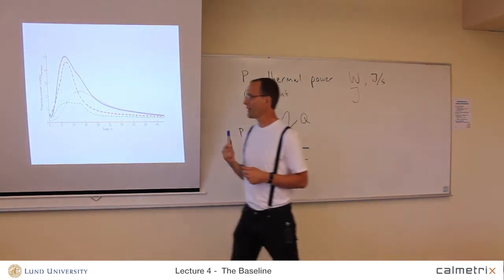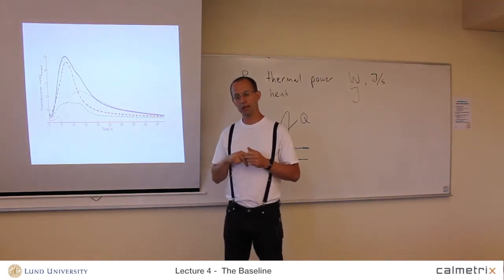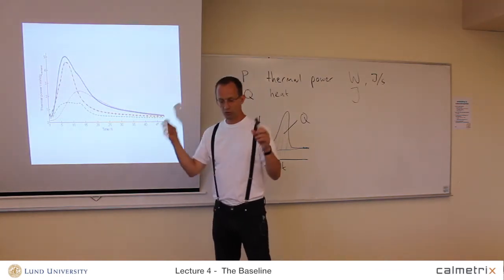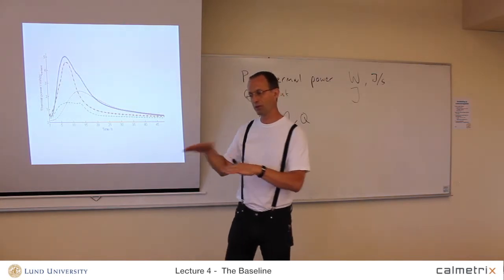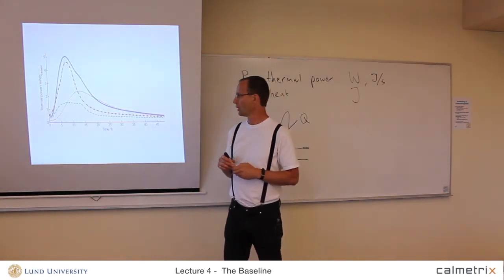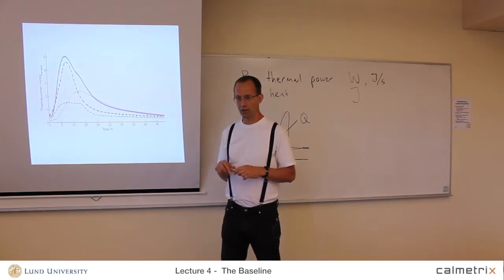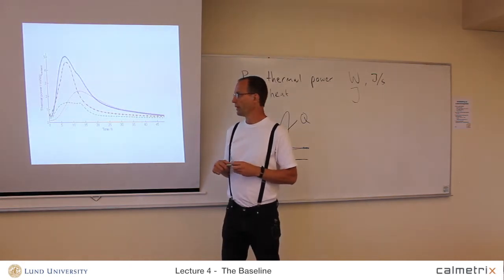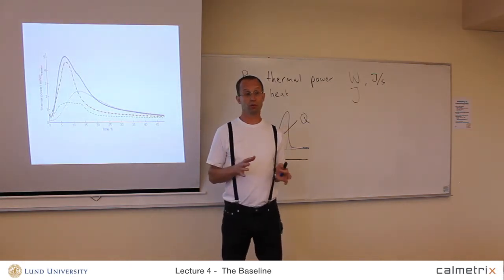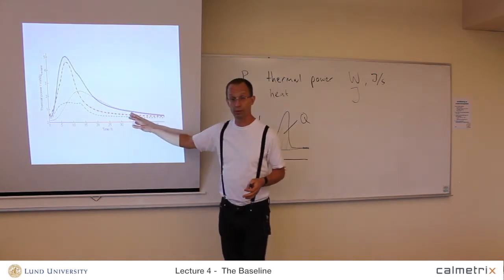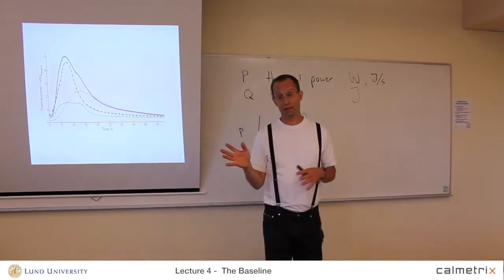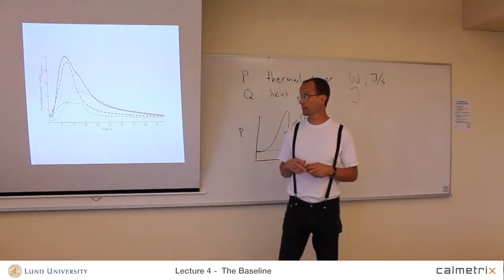To measure good baseline values, one should measure for quite a long time — at least 24 hours — because when you put things into the calorimeter there can be some initial disturbances. So measure for at least one day. On the other hand, baselines are usually very stable, so you don't need to measure them every time you do a measurement. I will come back to how often you should calibrate and measure baselines.